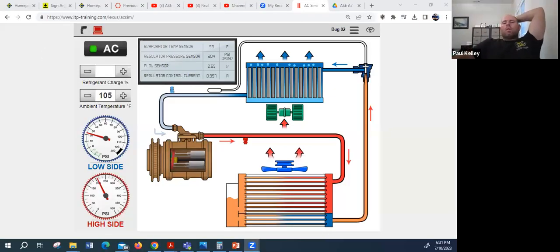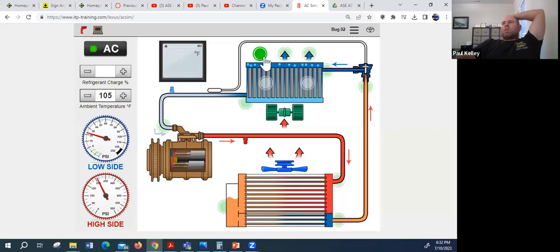Alright, so we'll jump in there, screen 2, bug number 2, let's go through the diagnosis. If we turn the AC on, you'll notice we're getting 200 on the high, 22 on the low. We can see about 59 evaporator, 204 high side. Flow sensors and regulator control current, I think that means this thing is running maximum stroke and it's got a medium amount of flow. So if we change over to the temperature...